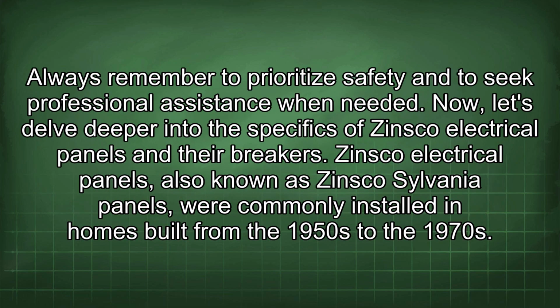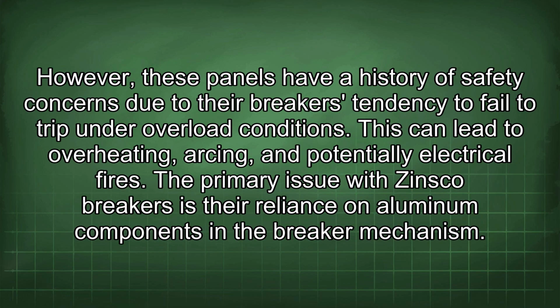Always remember to prioritize safety and to seek professional assistance when needed. Now let's delve deeper into the specifics of Zinsco electrical panels and their breakers. Zinsco electrical panels, also known as Zinsco Sylvania panels, were commonly installed in homes built from the 1950s to the 1970s. However, these panels have a history of safety concerns due to their breakers' tendency to fail to trip under overload conditions. This can lead to overheating, arcing, and potentially electrical fires.